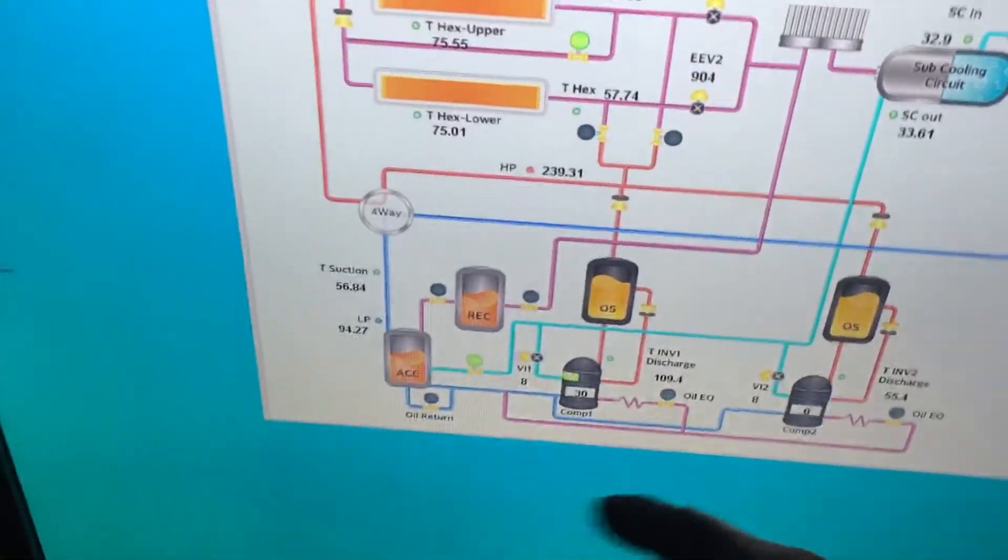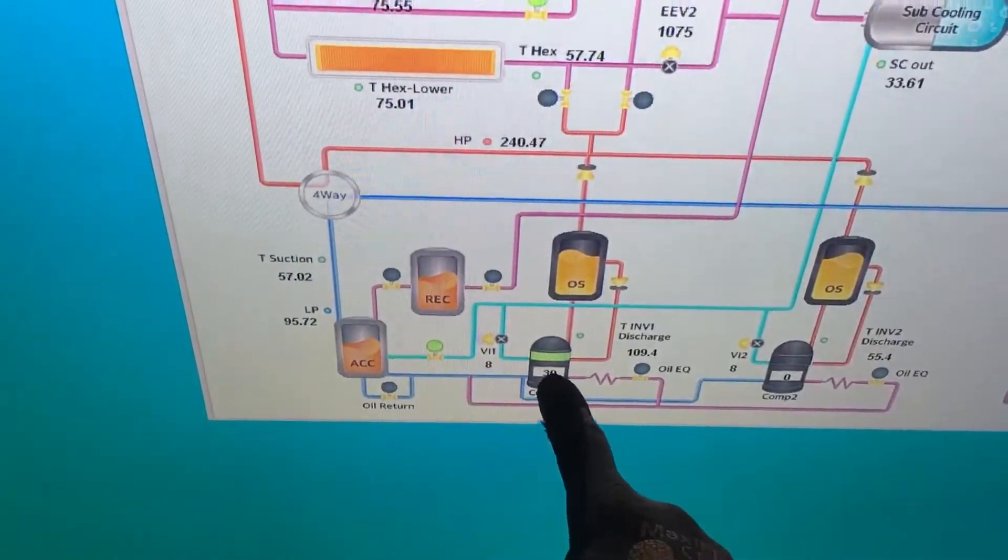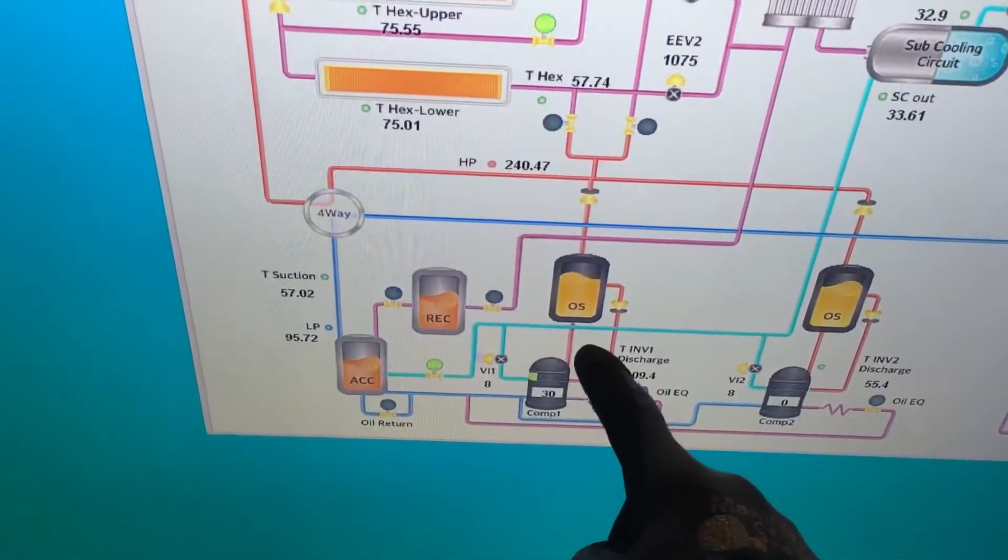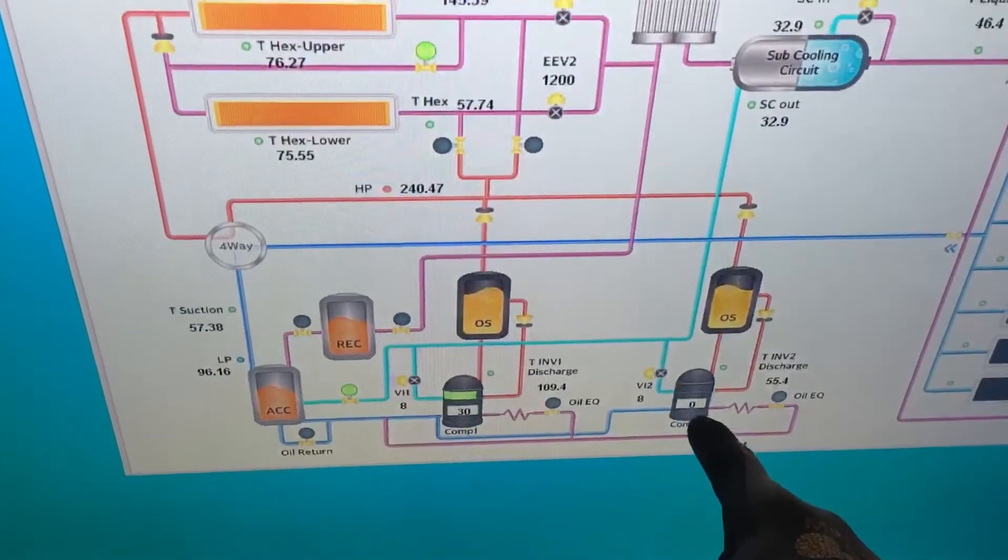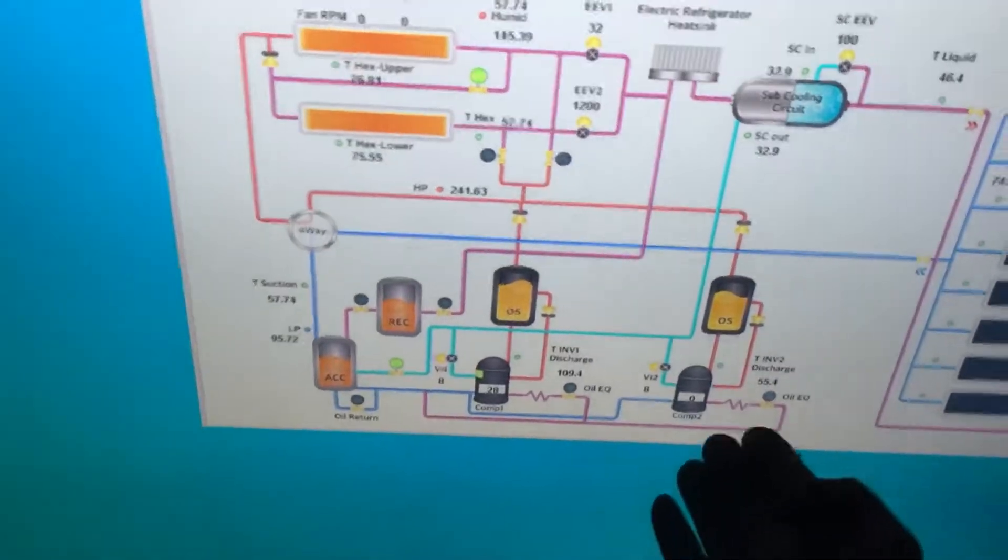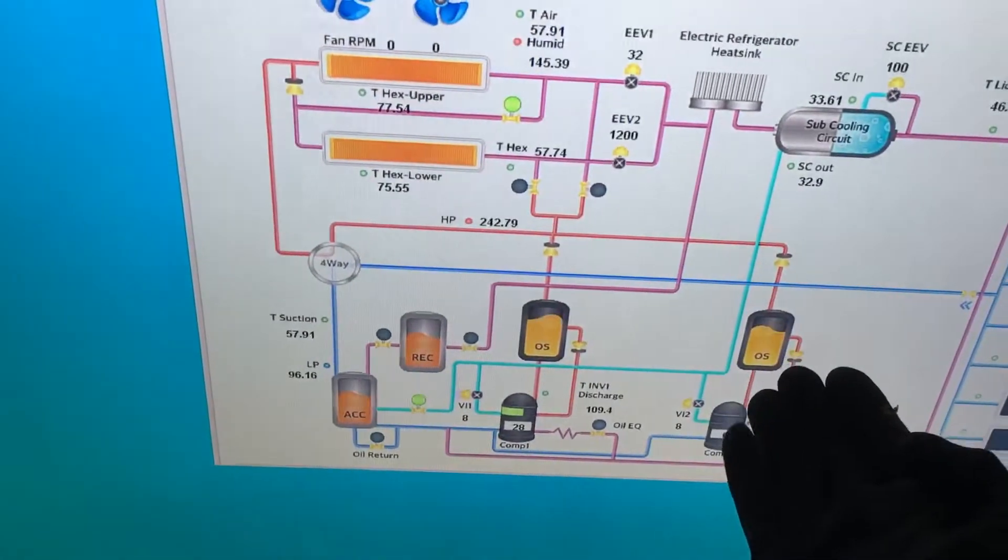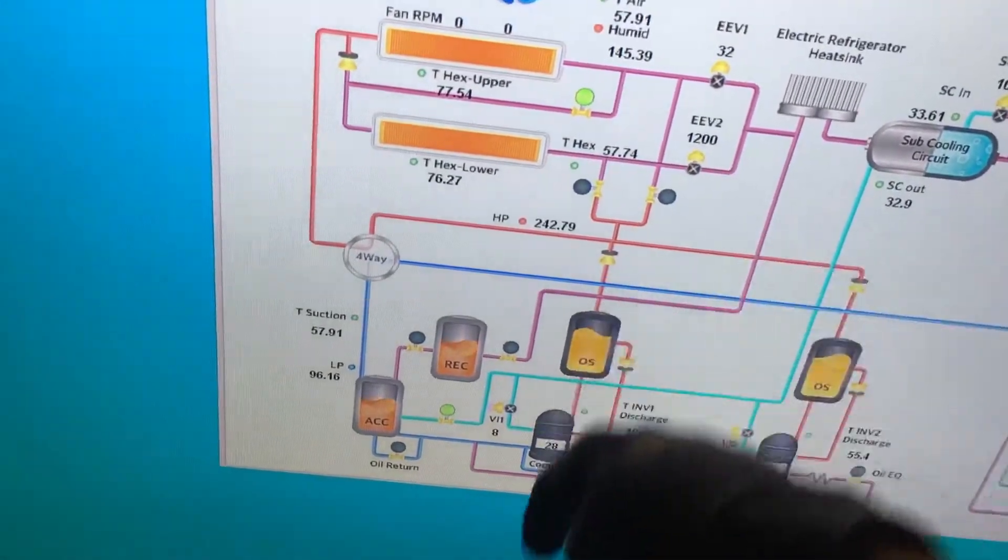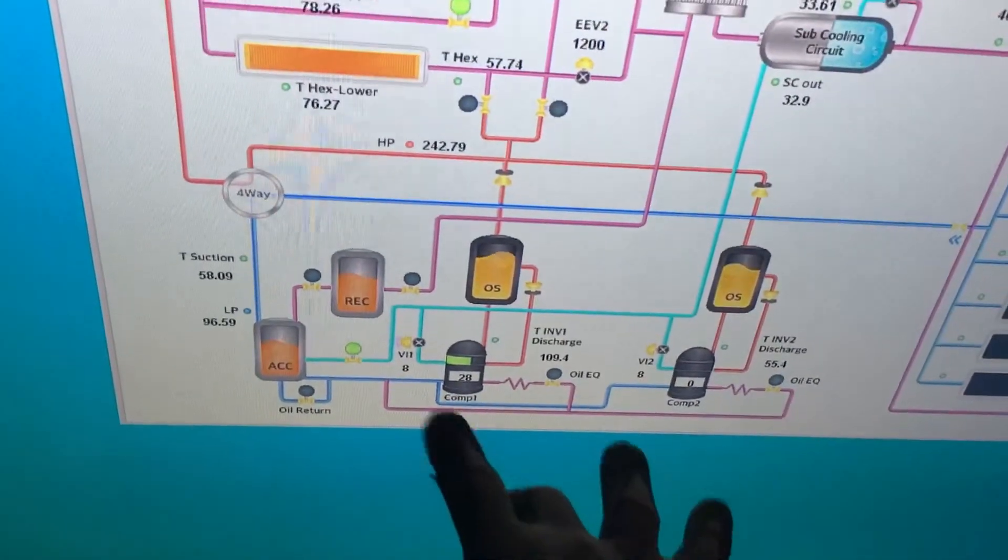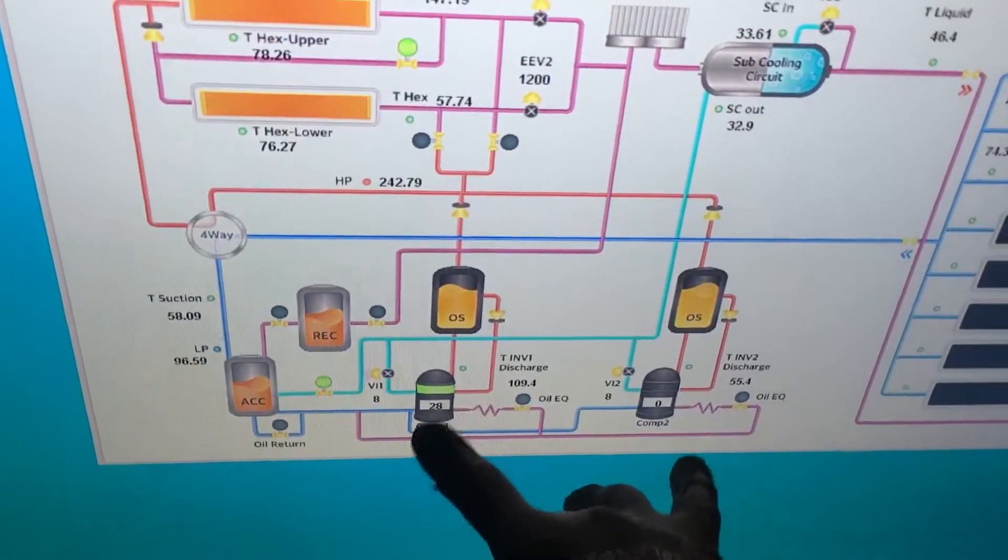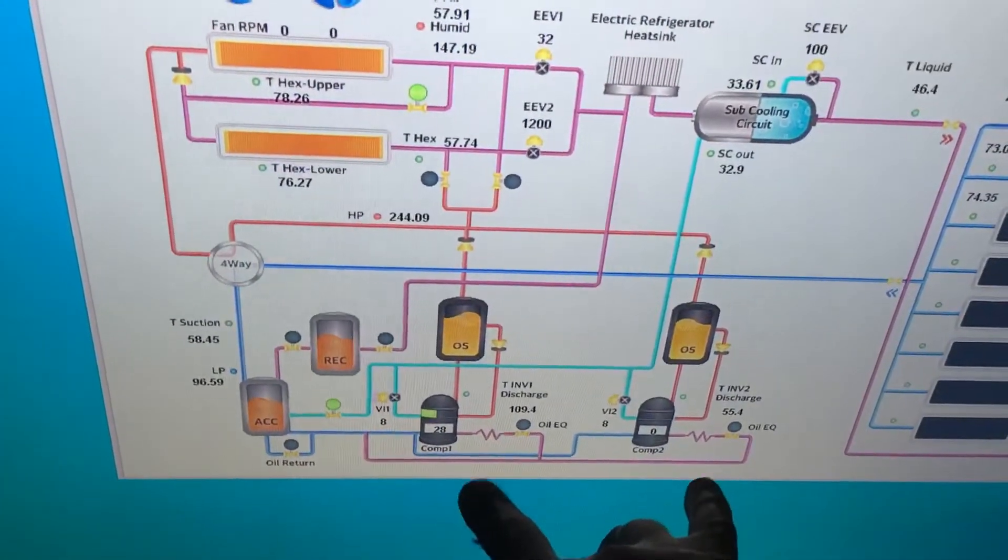It'll keep ramping up and then it'll kick in compressor number two. When it kicks in compressor number two, compressor number one will go down, and what it'll do is it'll split the load between the two compressors.